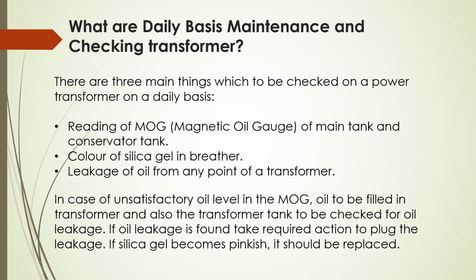In case of unsatisfactory oil level in MOG, oil is to be filled in the transformer and also the transformer tank to be checked for oil leakages. If the oil leakage is found, take required action to plug the oil leakage. If silica gel becomes pinkish, it should be replaced.